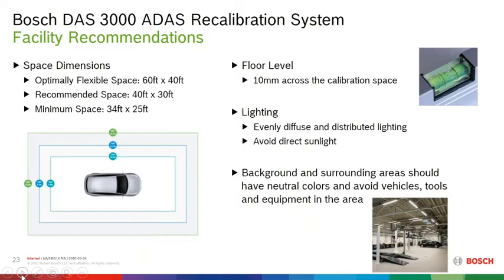And then there's the requirement for floor levelness. We recommend a floor levelness of 10 millimeters across the calibration space. Lighting should be evenly diffused and distributed. Really avoiding direct sunlight. Blocking out any kind of windows to avoid that sunlight coming in and affecting the calibration as it's happening. And then lastly, the background and surrounding areas should be a neutral color. Avoid any kind of checkered flags. A lot of times, shops will have checkered flags up for racing trophies, things like that. Make sure those are not visible during the calibration.